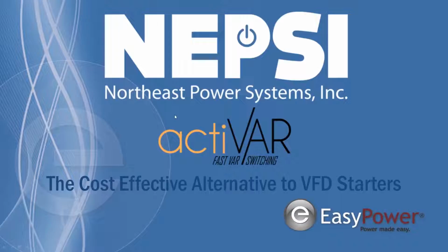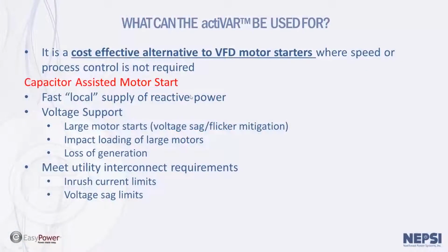So for today's discussion, we're going to talk about the actiVAR. The actiVAR is a cost-effective alternative to VFD motor starters where speed or process control is not required. It is basically a capacitor-assisted motor start, but instead of using conventional switches or circuit breakers, we use thyristors or thyristor valves. The actiVAR is a fast local supply of reactive power.